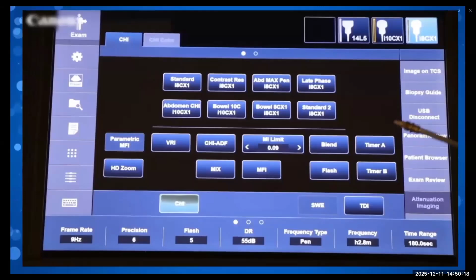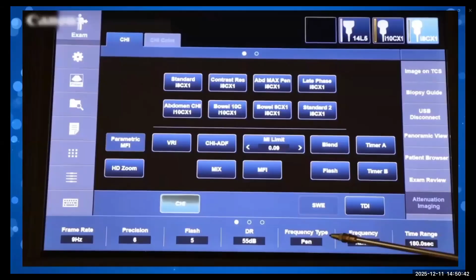The frequency type is at the bottom of the panel here, and here we have it set on penetration mode. You want to be aware of your specific frequency types before starting any exam. So prior to starting your contrast, it's really important to be aware of the knobology and the buttons that you will need in order to produce an optimal display.